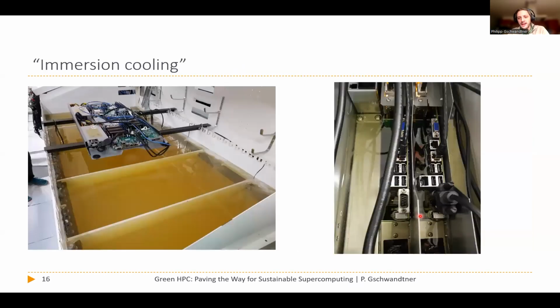That's one reason. Another reason is at some point they started to have network failures, and it was really curious because the network switches were not oil cooled. So what you have here is oil creeping up into the network cabling infrastructure and creeping along the network lines outside of the tank into components that were never oil cooled to begin with or never intended to be oil cooled to begin with.